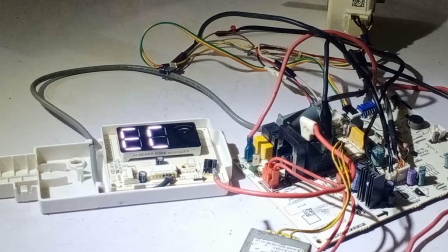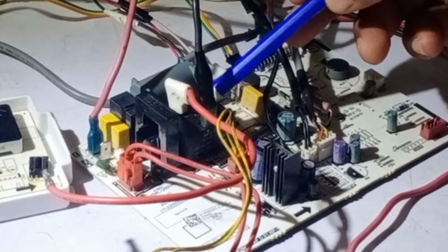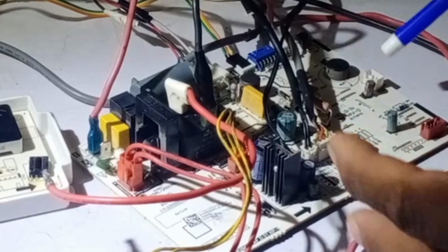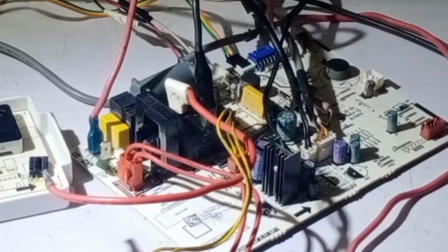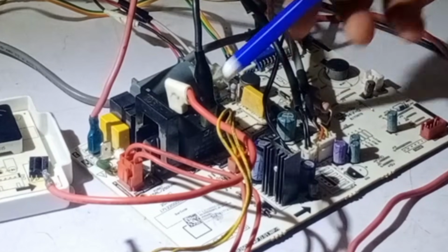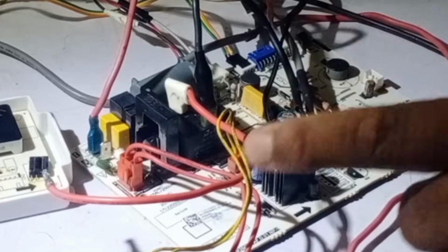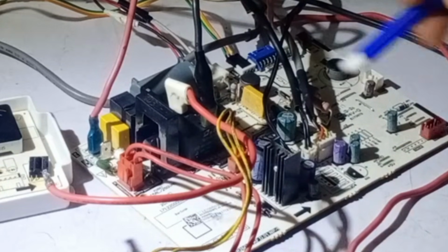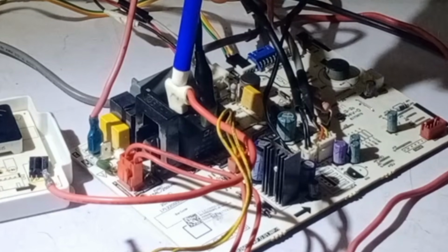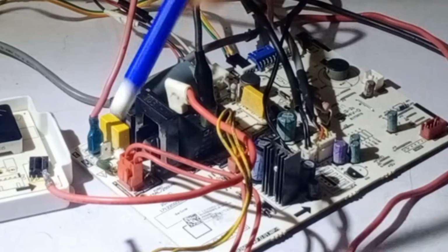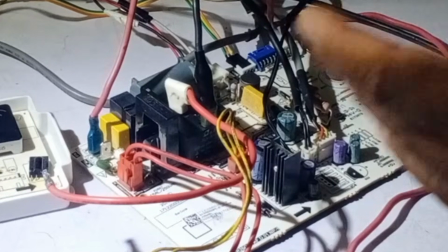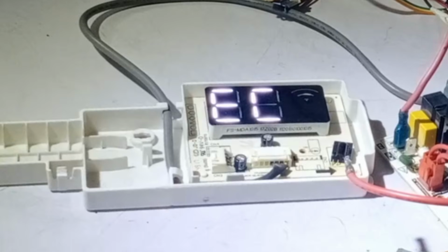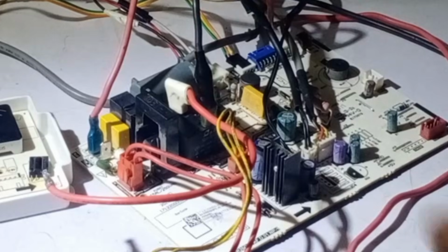Other than this, let me tell you that a bigger difference in the EC error code between the inverter and non-inverter is that a relay is installed on the indoor circuit board. The microcontroller has turned on the relay. The relay is magnetized, and then 2 non-connected pins come in contact. If the carbon is built up on those pins, the electric supply in the unit has been turned on, but it could not supply it out. At the same time, the microcontroller has done its job. The supply is not moving forward, and the unit is not able to turn on. Still, due to that reason, it will show the EC error code. Then you will have to check whether the relay is faulty or the electricity is not passing from here.